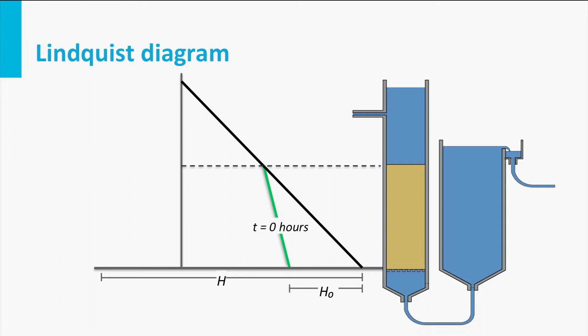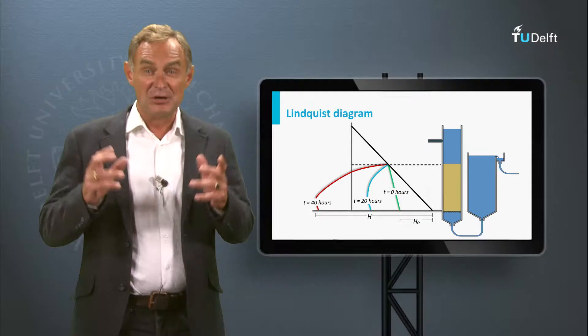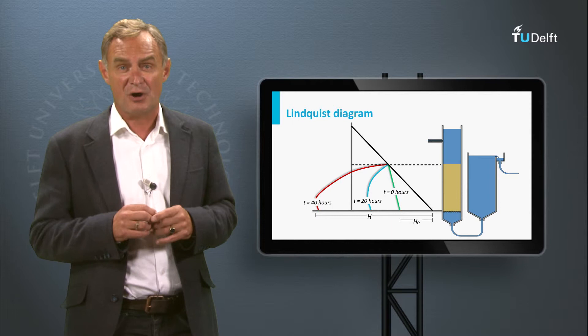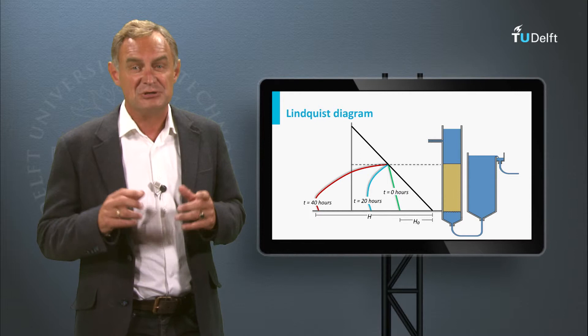With increased clogging, the pressure in the filter bed decreases until pressures below atmospheric can occur — the so-called negative pressures. These must be avoided because of the risk of degassing and consequent disturbance of the filter bed. The maximum allowable filter bed resistance is thus dependent on the occurrence of negative pressures.